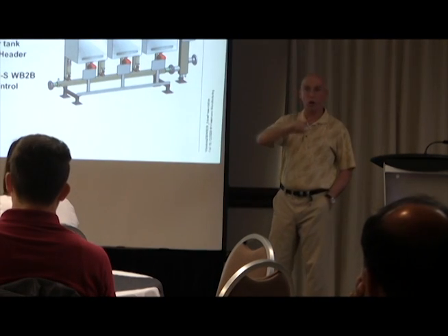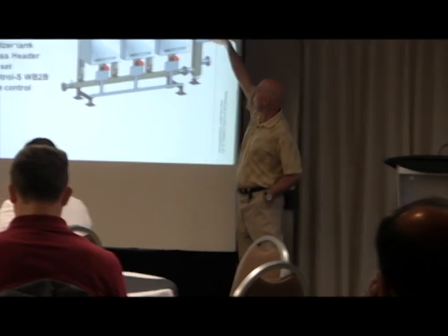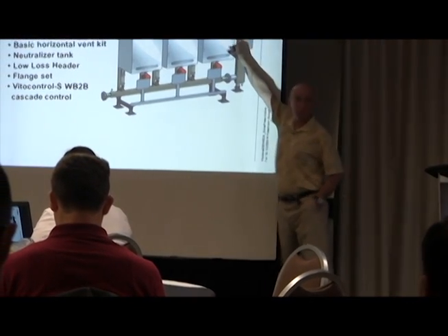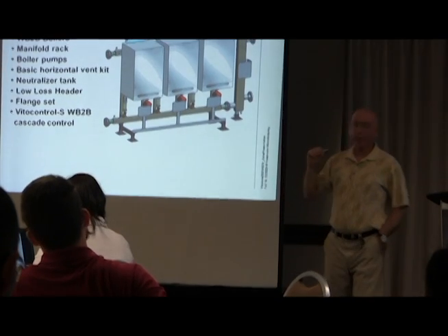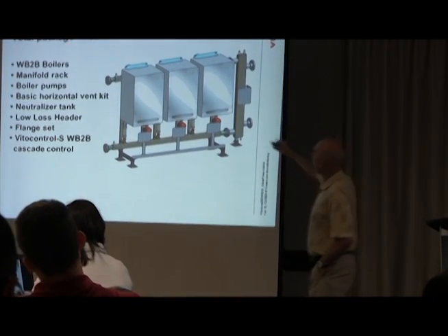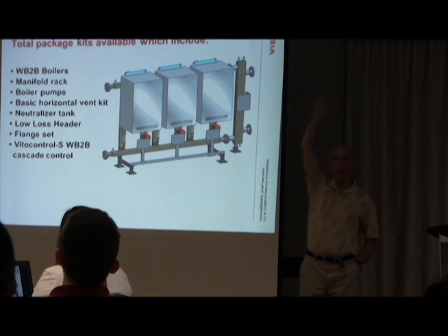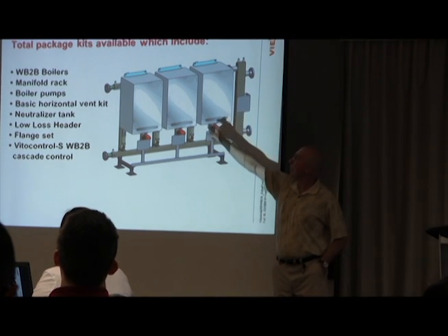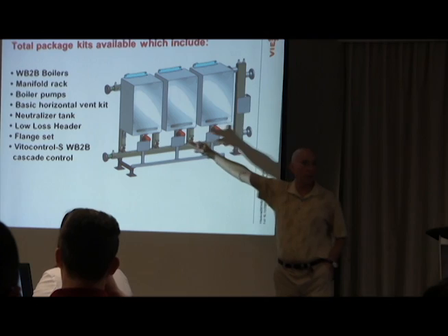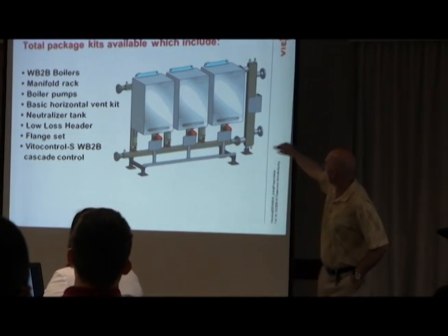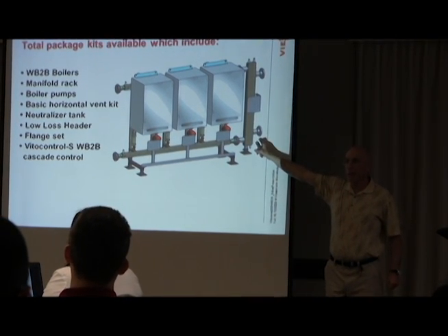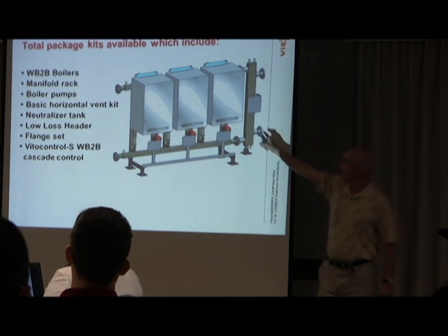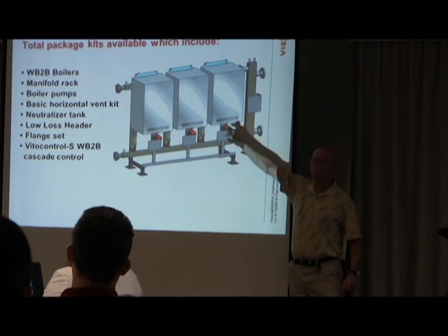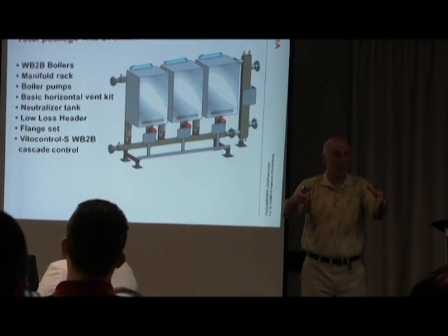Another advantage is the sensor. There's a common supply sensor that goes into the low loss header, reaching about midway down. This gives a more accurate temperature reading of what's going on in the system, rather than using the temperature sensors in the boiler heat exchangers. The advantage is it helps the boiler condense more, since you get better condensing ability with the sensor reading here instead of right at the heat source in the boiler.